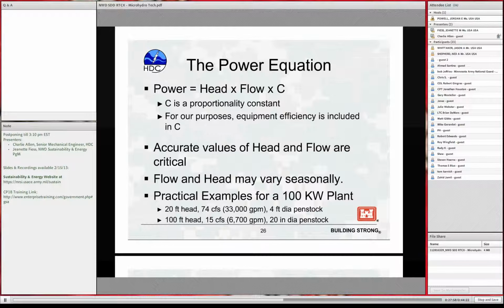Now let's go to what I call a power equation. Hydroelectric power, the amount of power generated, is simply equal to the head at the site times the flow at the site times a proportionality constant. And for our purposes, I've rolled the equipment efficiency into that proportionality constant. Head is the amount of the elevation and the difference of the water. Think of it perhaps as the height of the dam or the distance that a waterfall drops from the top of the water to the bottom of the water. Flow, measured in cubic feet per second, gallons per minute, doesn't matter. All it does is change the proportionality constant. Obviously, accurate values of head and flow are critical to determining what your power potential is at the site.